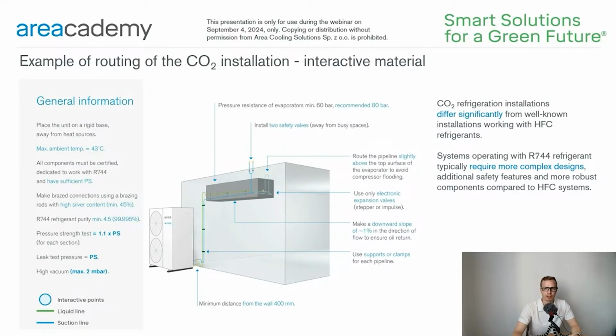On this drawing, you can see a simple one-to-one CO2 installation. We have one transcritical CO2 unit and one evaporator inside the cooling or freezing chamber. CO2 refrigeration installations differ significantly from well-known installations working with HFC refrigerants. Such systems typically require more complex design, additional safety features, and more robust components compared to HFC systems. Therefore, we have prepared an interactive material that contains the most important information on how to route a CO2 installation. It is available for free on the Areacademy website, like all the other digital materials and articles we publish there.